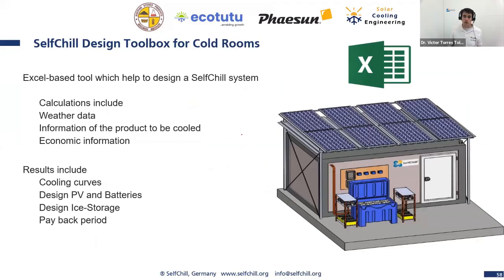Okay, so we are coming to an end. As an introduction, what we will do in the next webinar, we will go through the design process of a cold room like this one. We will figure out, okay, how many products are we entering per day inside the cold room? Is it, for example, going to be 500 kg per day? What is the ambient temperature, the weather conditions, and what is the size of the cold room? And based on this, we will do the calculation of the cooling load. We will have a look at the weather data, so that at the end of the day, we can calculate the results that include the cooling curve, how fast the products are going to be cooled down.